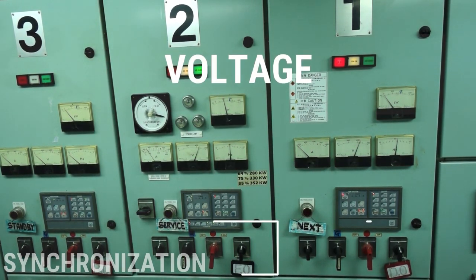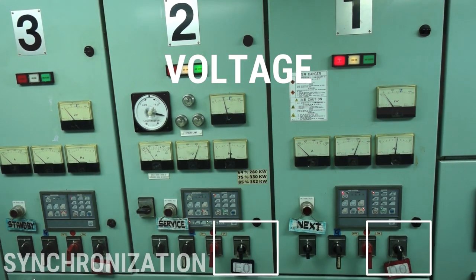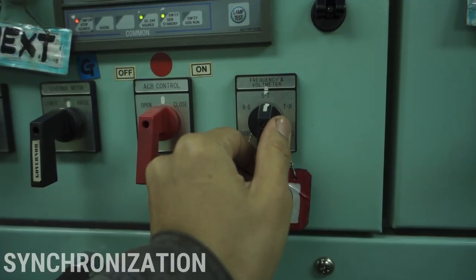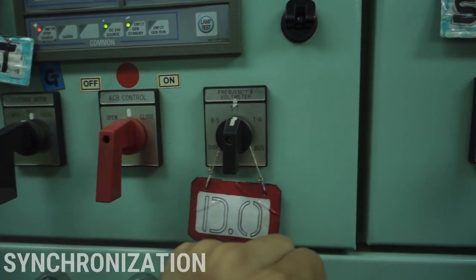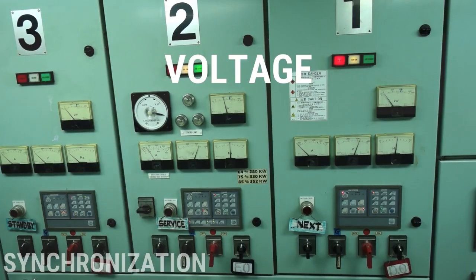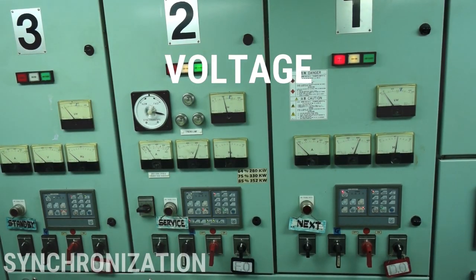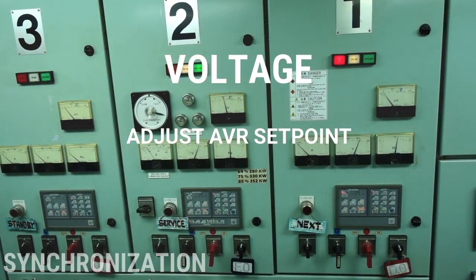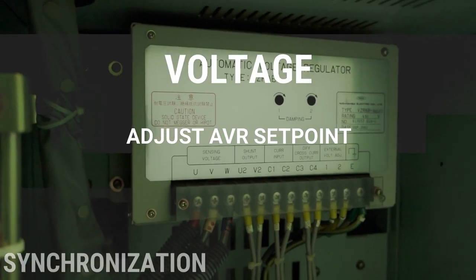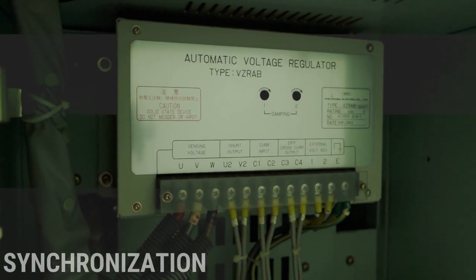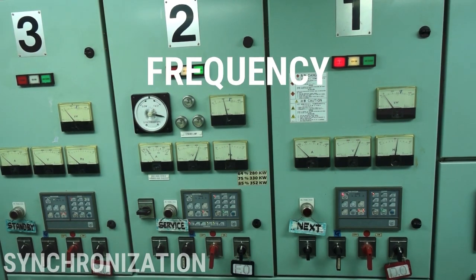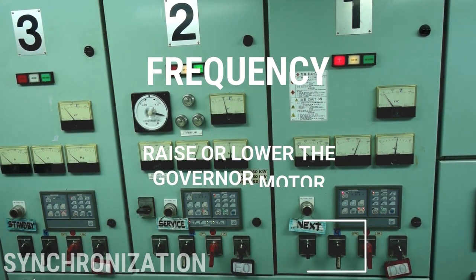For voltage, make sure that the selector switch for voltmeter and frequency are selected to the correct generator. Check if they are equal. If not, you can manipulate the voltage of the incoming generator by adjusting the voltage regulator. For frequency, you can manipulate it by adjusting the speed of the prime mover through its governor.